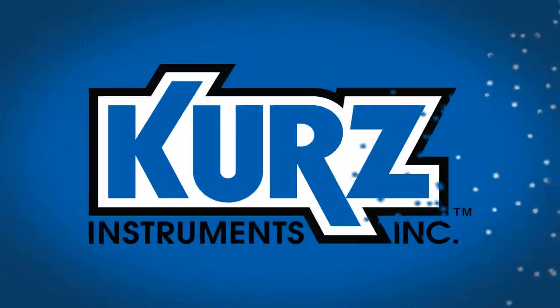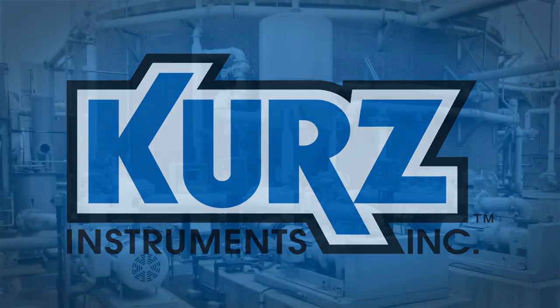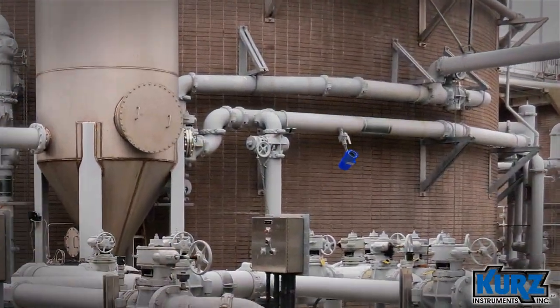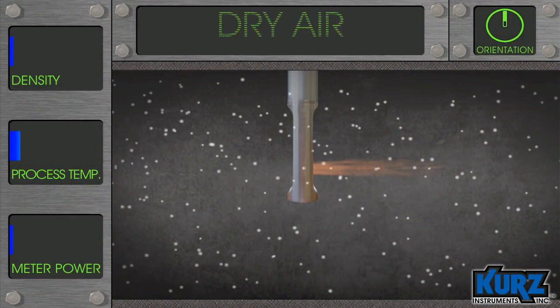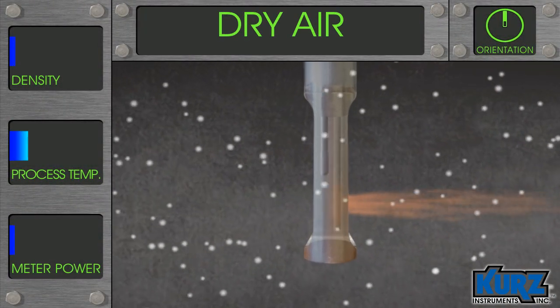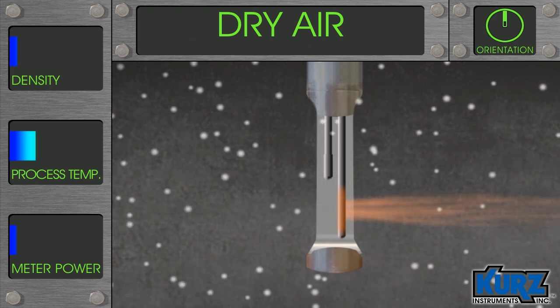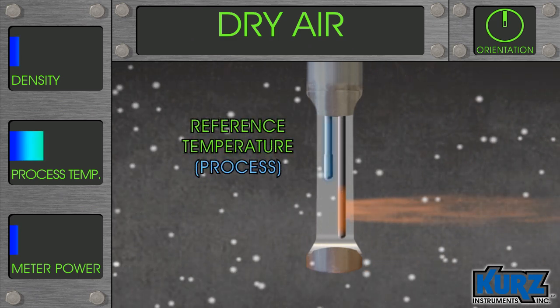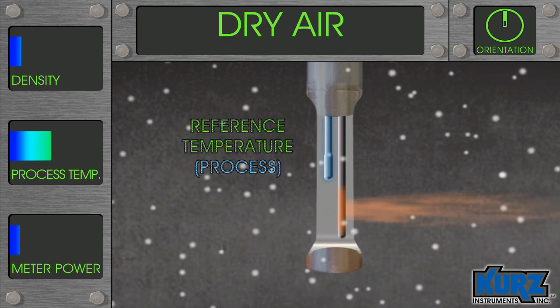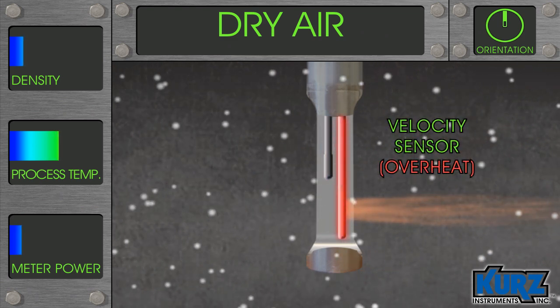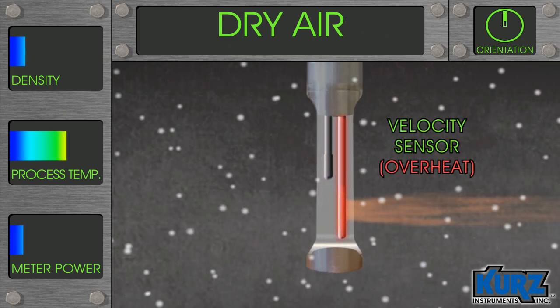Kurz Instruments manufactures thermal mass flow meters for dry and wet gas applications. A probe with two temperature sensors is inserted into the process flow. One sensor provides the process reference temperature. The other sensor is heated to a constant temperature above the process flow.